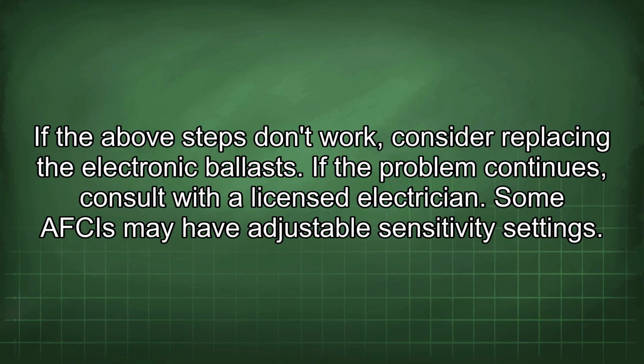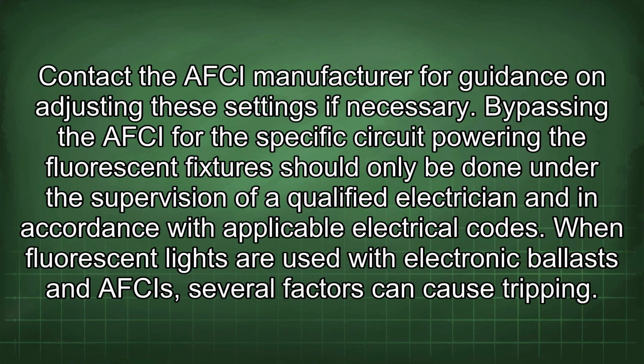Some AFCIs may have adjustable sensitivity settings. Contact the AFCI manufacturer for guidance on adjusting these settings if necessary. Bypassing the AFCI for the specific circuit powering the fluorescent fixtures should only be done under the supervision of a qualified electrician and in accordance with applicable electrical codes.